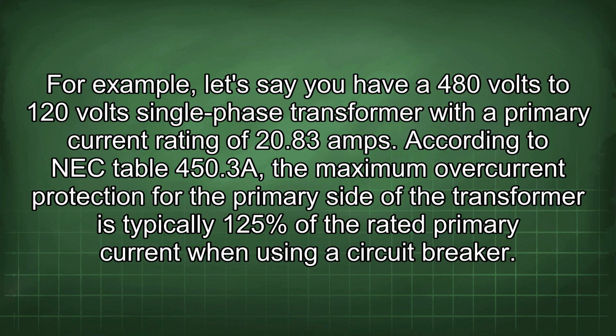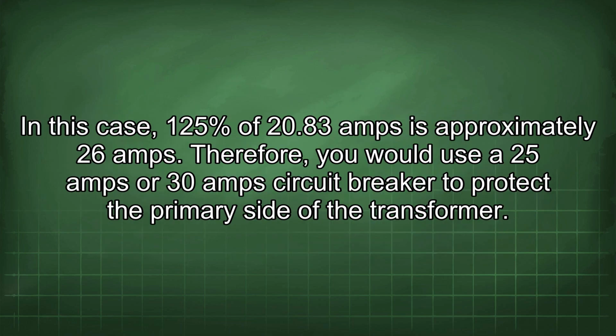According to NEC Table 450.3(A), the maximum overcurrent protection for the primary side of the transformer is typically 125% of the rated primary current when using a circuit breaker. In this case, 125% of 20.83 amps is approximately 26 amps. Therefore, you would use a 25 amp or 30 amp circuit breaker to protect the primary side of the transformer.